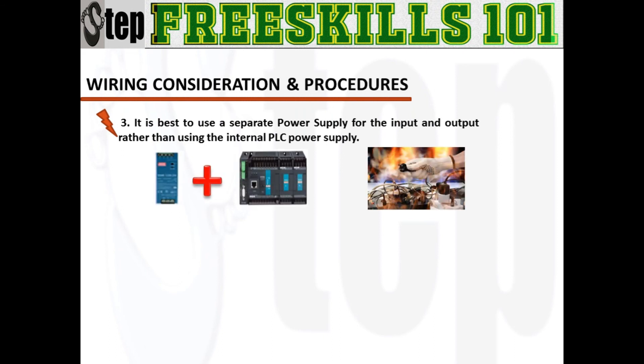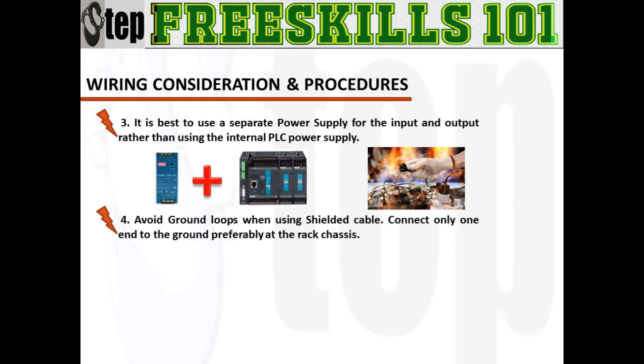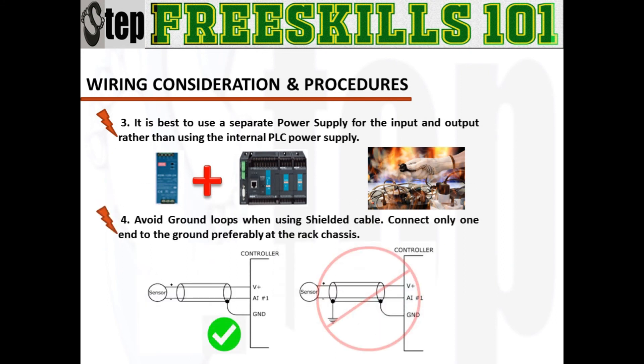Having a separate power supply would prevent direct damage to the PLC when overloading occurs. Later on, modifications and add-ons can occur in a control panel, so having a separate power supply can give you more flexibility for any changes. Ground loops are a major cause of noise, hum, and interference in audio, video, and computer systems. So avoid ground loops when using shielded cable — connect only one end to the ground, preferably at the rack chassis.